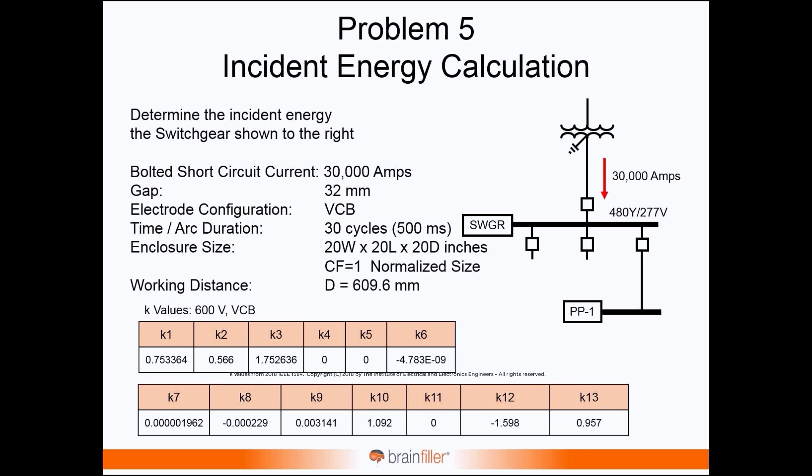The enclosure size — the default enclosure size from back in 2002 for switchgear was 20 by 20, and we're going to stick with that. The nice thing about this problem is that using the 20 by 20 enclosure size is the default value. If you don't make any correction for different heights and widths, the default is 20 by 20, so we don't have to address the correction factor for enclosure size.